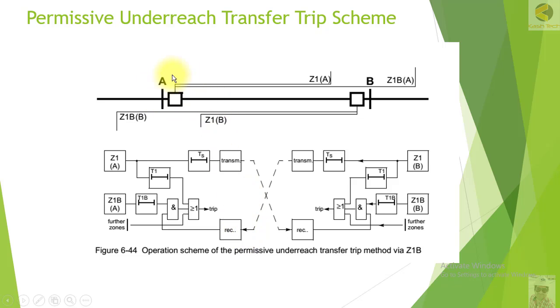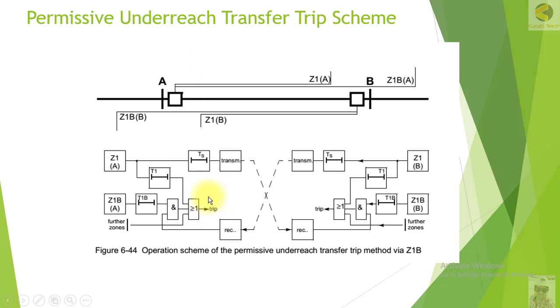Station A's relay is waiting — it is effectively in Zone 2, so the Zone 2 timer of 400 milliseconds has started. When it receives the signal from Station B and checks — using the AND gate — whether it is also picked up in the forward direction at Z1B, if the fault is within Z1B, the relay at Station A picks up and both inputs are high, so Station A trips immediately.